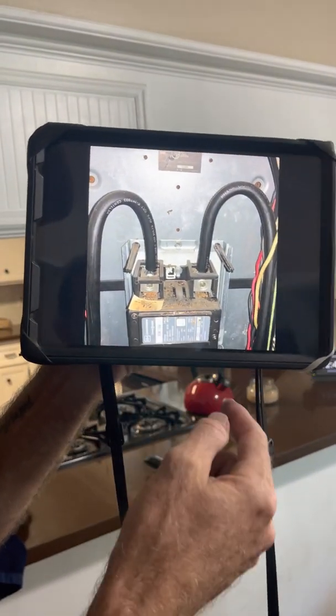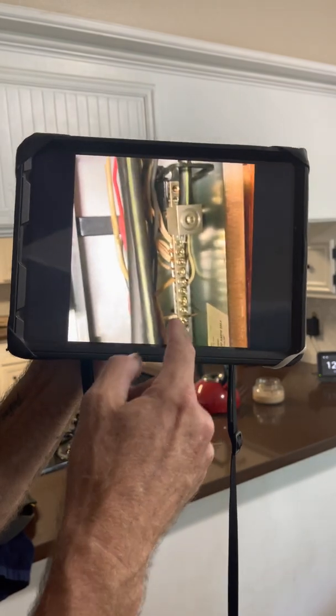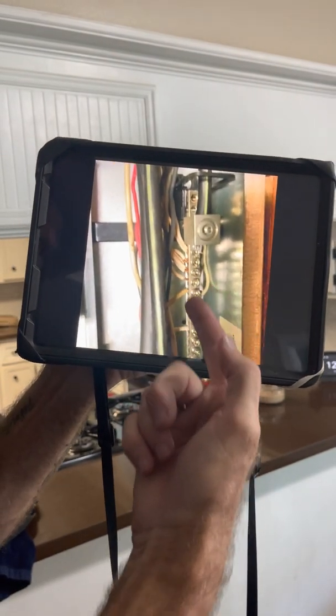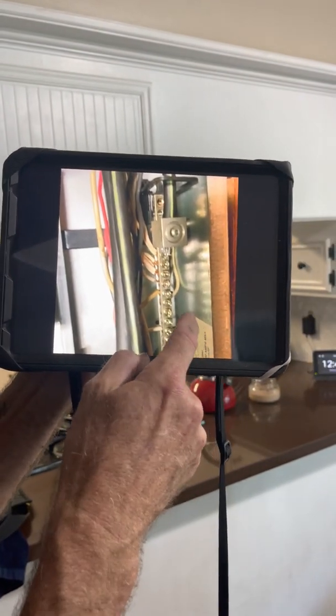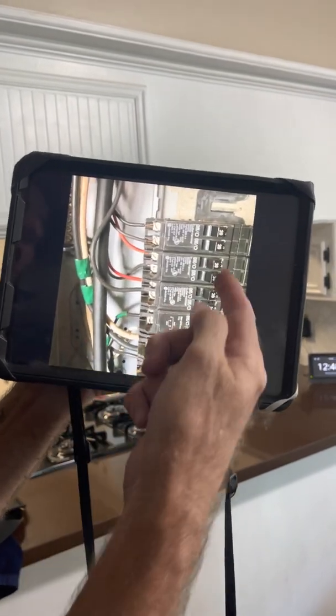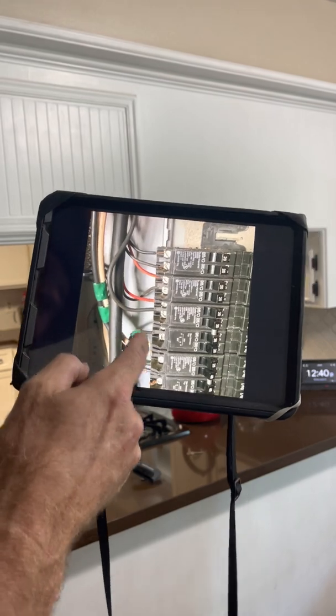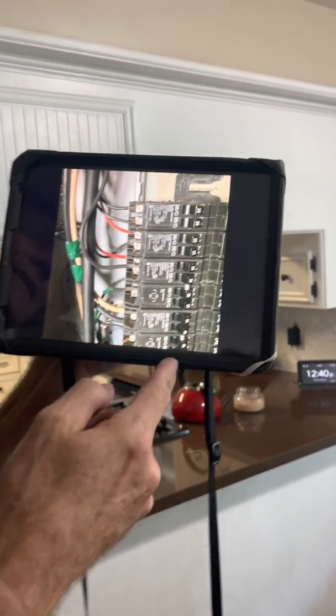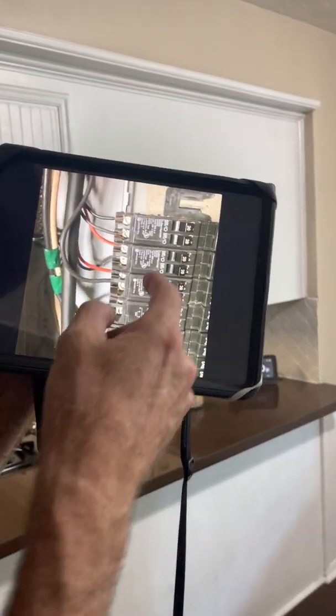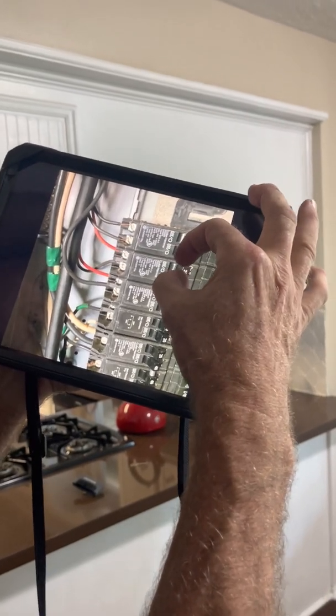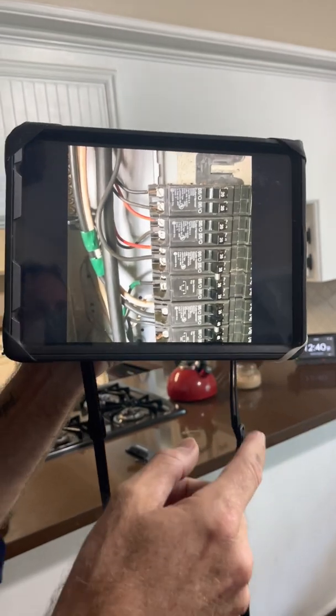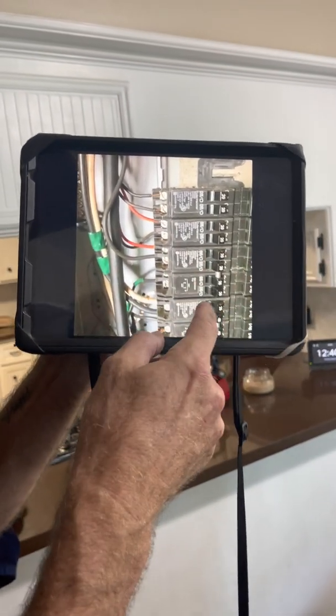Today's world, we have to talk about anti-oxidizing grease, that's an update. Today's world, we don't get to land two wires under one screw, that's an update, it's called double tapping. Today's world, these breakers should be tied together. Anytime you see a black and a red wire together, that's called a shared neutral. So these are supposed to be shared so that both of them trip when one trips, because it's on the same neutral. These are all update items.